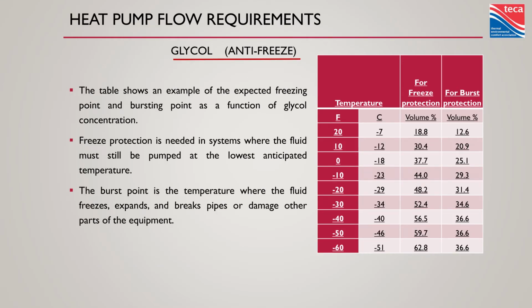Glycol has freezing points and bursting points. When you're selecting your glycol, bursting is not the one you're looking at. It is freezing. Once the water is frozen, it doesn't move around very well. I don't care that the pipe didn't break. We can't transfer heat through a slushy. So look at the freeze protection numbers, and you're usually going to be in that 20 to 30% range depending on where you're installing it, but less is more.